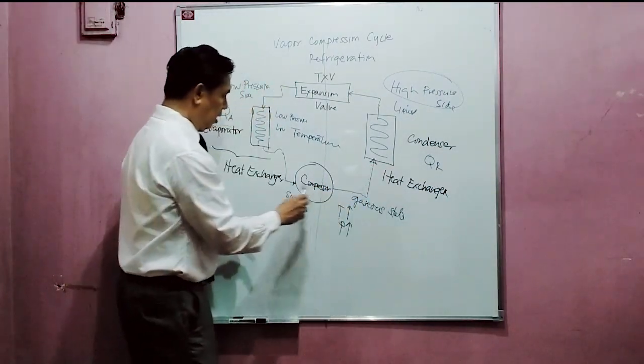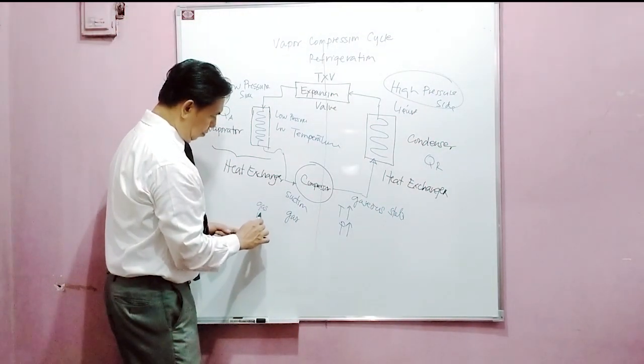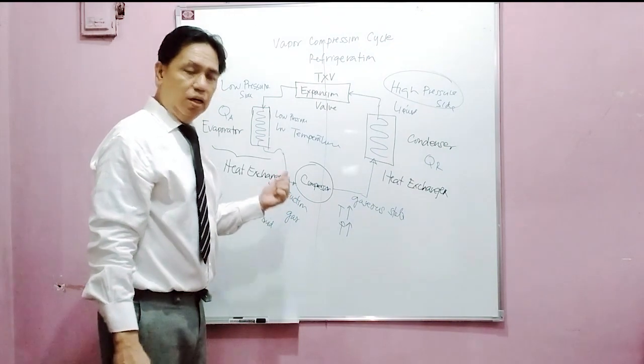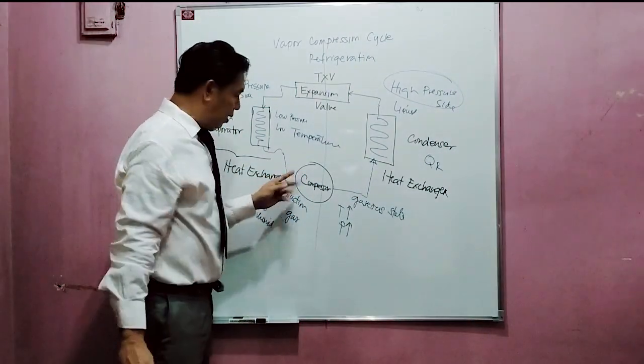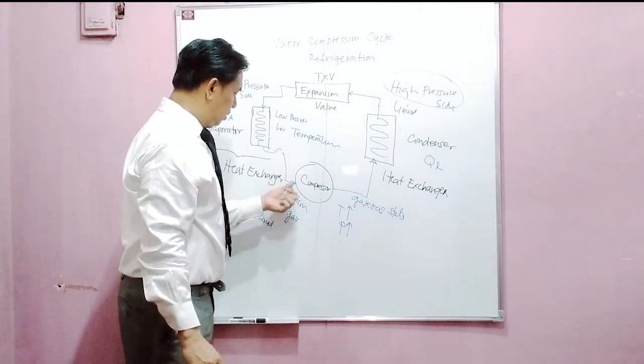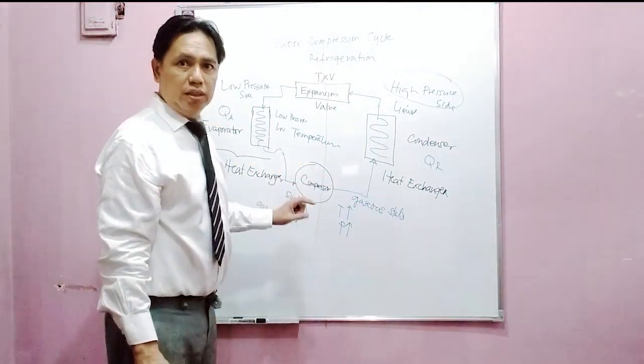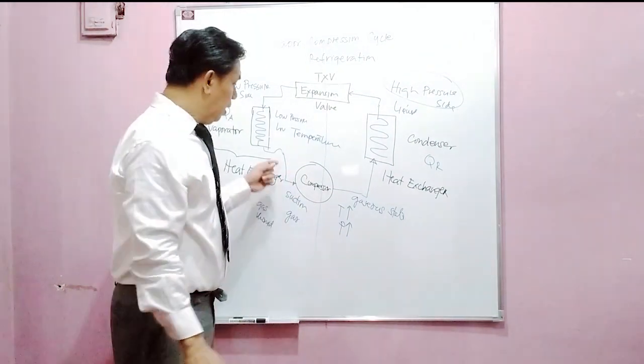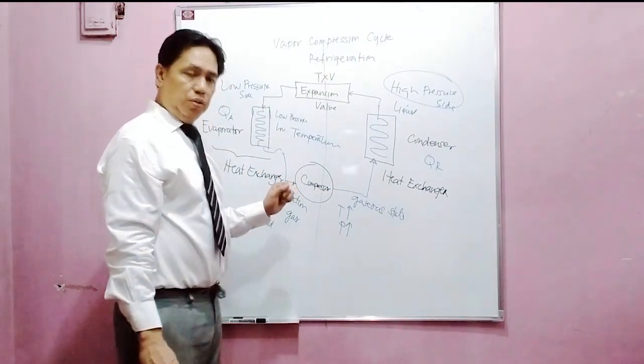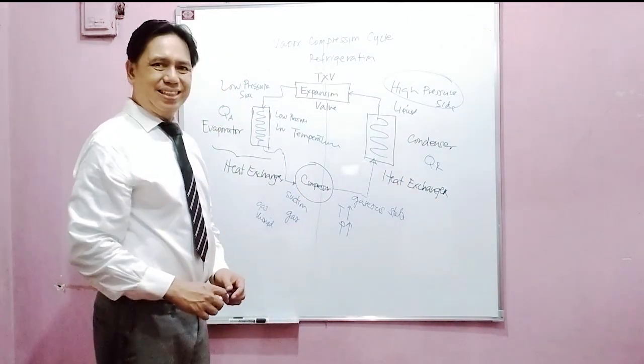Here there is a mixture of gas and liquid, but normally it will be ideal if the refrigerant entering the compressor is in saturated vapor form — it would be better because liquid cannot enter the compressor. It will break down the parts of the compressor. Only vapor should be what the compressor compresses into higher temperature.